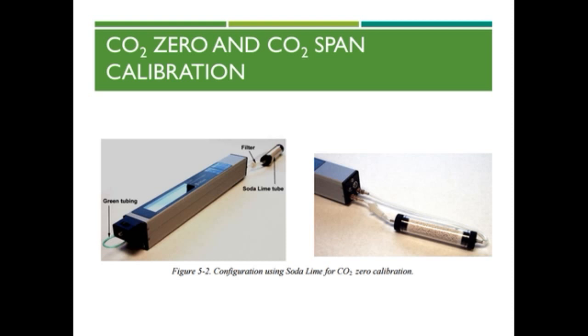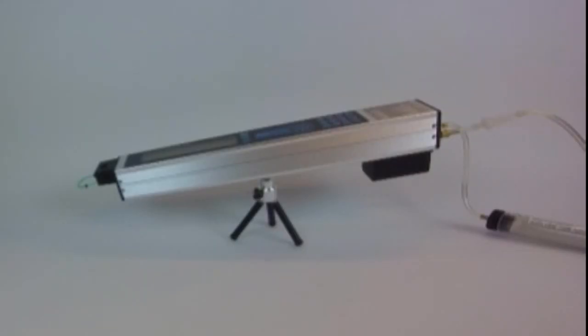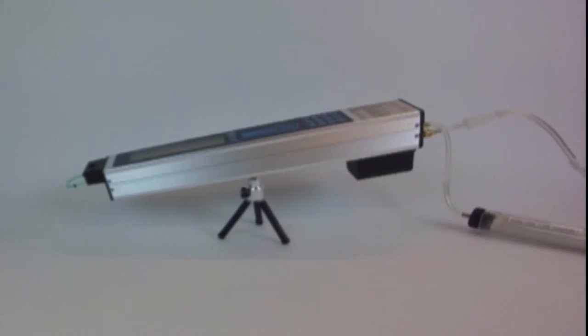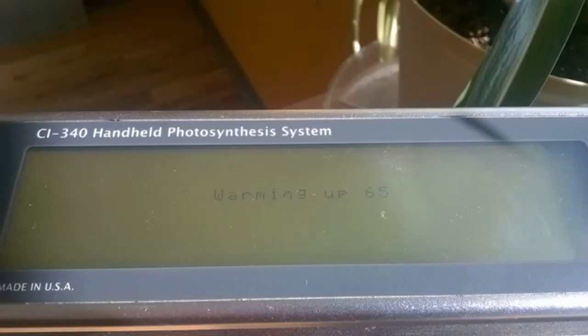Insert the loop-back green tubing with the 2 rubber O-rings into the valves where the leaf chamber normally attaches. The loop-back tube ensures there is no opportunity for leaks during the calibration. To zero the CO2 sensor as an example, power on the instrument and connect the green loop-back tube. Connect the soda lime tube or set the AD CO2 and H2O to 0. Use the up and down arrow on the main screen to navigate to Calibrate CO2. Press Enter. The instrument will begin warming up.